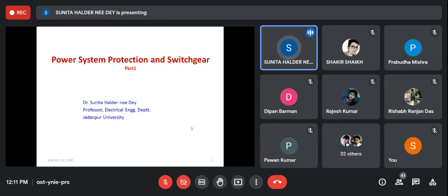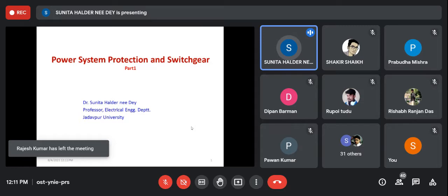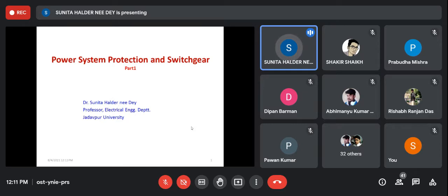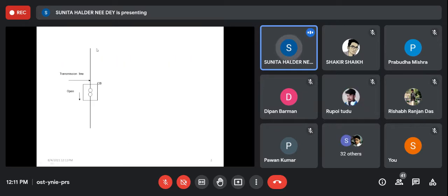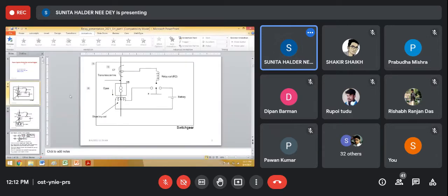So if we think about short circuit, one device should be there that will monitor the system current at every moment, and it will initiate a signal when there is any abnormality in current, if there is any hike in current due to short circuit. And there will be another device which will disconnect the healthy part of the power system from the unhealthy part. So if we think about a transmission line, we have learned that there is a transmission line connecting two substations or two power system buses. Now the transmission line also has protective devices.